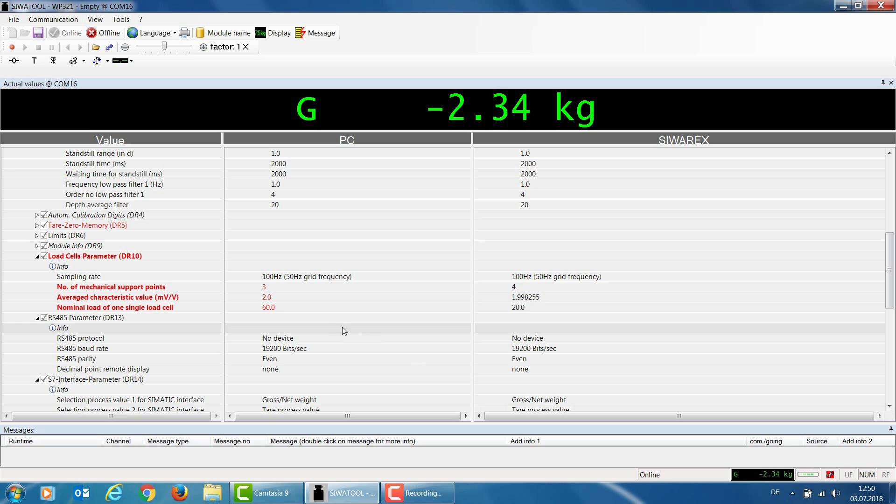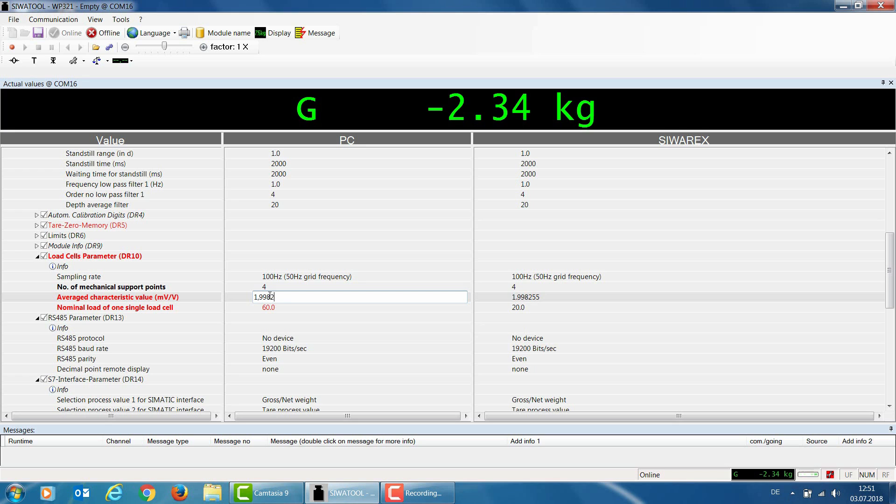Data record 10 is used for parameterization of automatic calibration. First, we define the number of mechanical supports — in my case, I have a container with 4 load cells, meaning 4 support points, so I set this parameter to 4. For the next parameter, average characteristic value, I enter the characteristic value of the load cells. When using multiple load cells, specify the mean value — in my case, this is 1.998255 millivolts per volt. I then specify the nominal load of one load cell, which in my case is 20 kg each across 4 load cells.